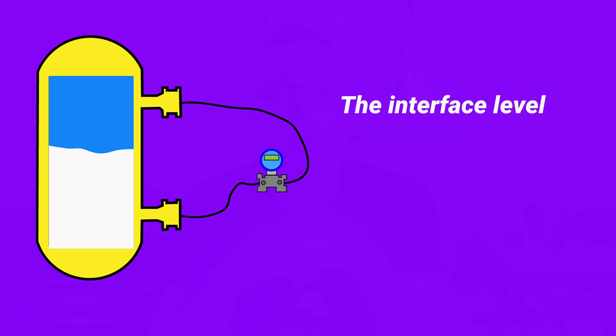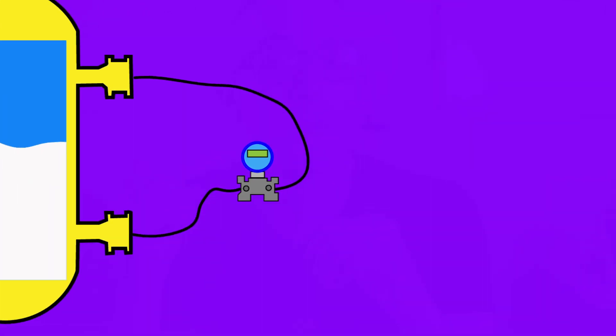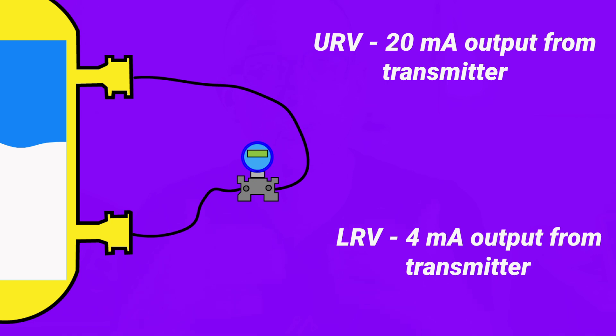Now just like every level transmitter there are only two numbers that it needs in order to measure this level correctly. Those two numbers are the lower range value and the upper range value, the LRV and the URV.